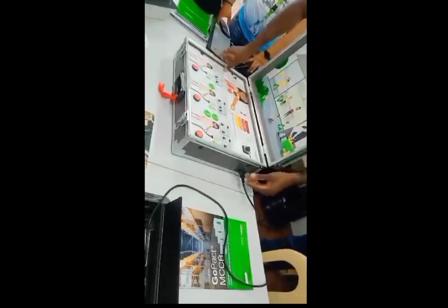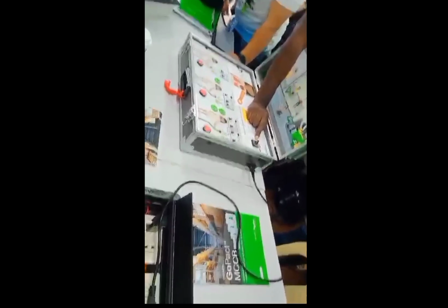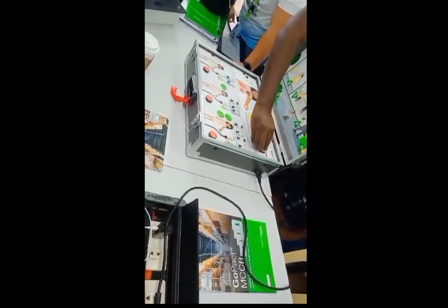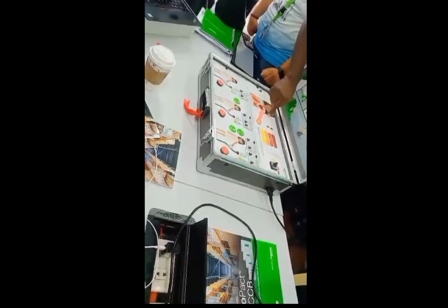Studies the levels of electrical current that can harm the human body. So this just displays what the study from IEC shows. So 2 milliamps of current, which is 0.002 amps, is already enough for you to feel this level of current flowing through you. This doesn't cause any irreversible damage, but you can already have sensation in your fingers. Now 10 milliamps is sufficient to result in muscle contractions, but again, this does not cause any irreversible damage to the human body.